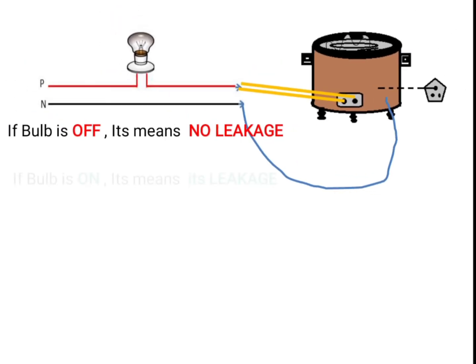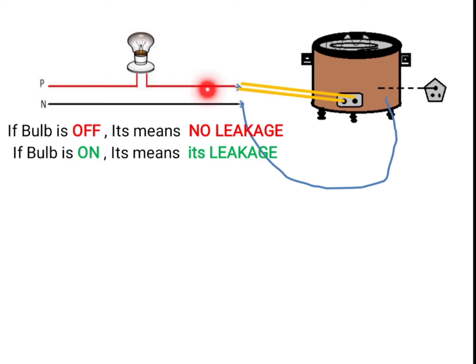If the bulb is on after doing this connection, that means there is a closed circuit. That means one of the terminals, either the wire, cord, or this part, is touching the body. That is why the circuit is closed and you will find the bulb on. So there is a leakage. Be very careful; you can get a definite shock, especially when the phase wire touches the body.